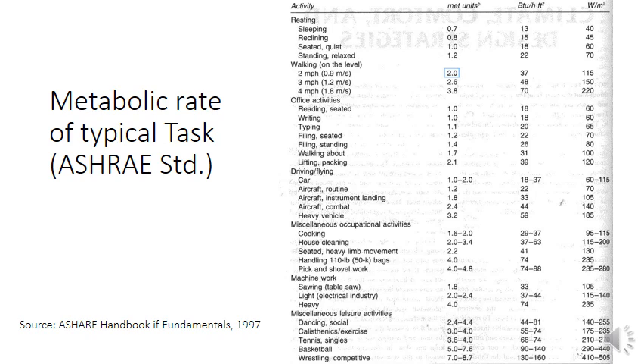This table is taken from the ASHRAE Standard Handbook of Fundamentals 1997, providing standard metabolic rates. The first column is activity, the second is metabolic rate in met units, then BTU/h, then W/m². For resting/sleeping the minimum activity is 0.7 met, equal to 40 W/m². Sitting quietly is 1 met; standing is 1.2 met. Walking at lower and higher speeds ranges from 2 to 3.8 met. Reading or writing sitting is 1 met; lifting or packing is approximately 2.1 met.